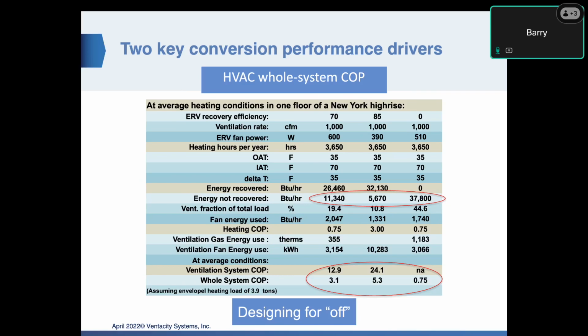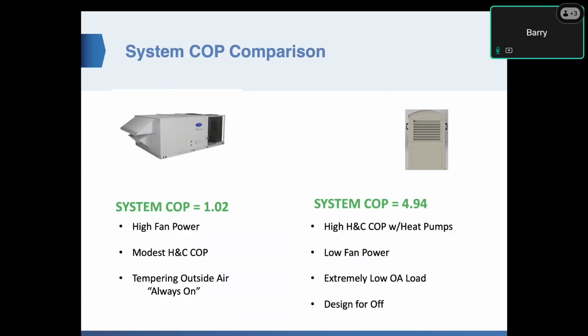Very high pump and fan power, zero, as far as the COP on the heat recovery, there is none. And so using very high efficiency at 85%, we were looking at a system COP of 5.3 as opposed to 0.75, which is existing. About 80% energy savings on this 50-story building. We did an analysis of that at the time. It was about $1 million a year in energy savings for the building. So this is how very high efficiency ventilation really has a huge impact when you're trying to do electrification decarbonization.